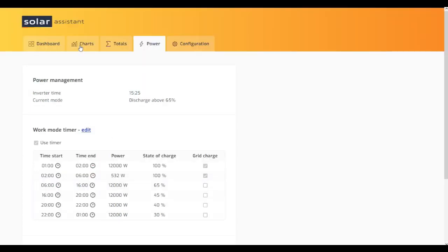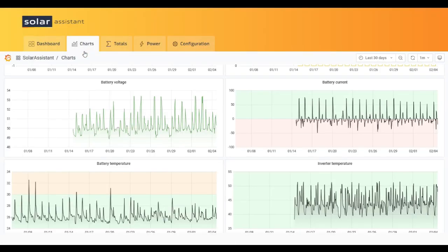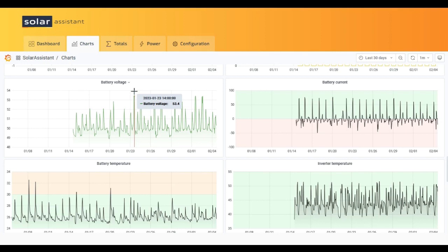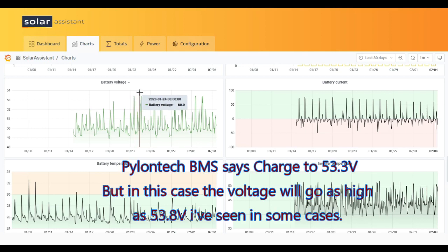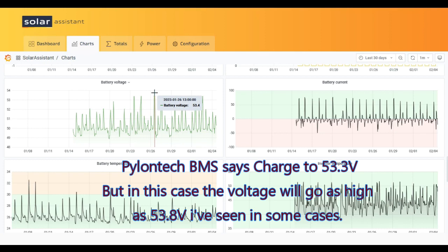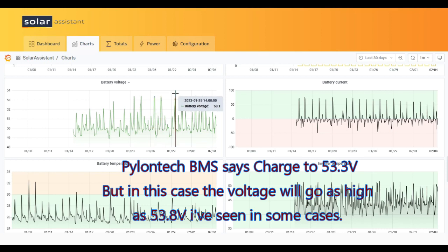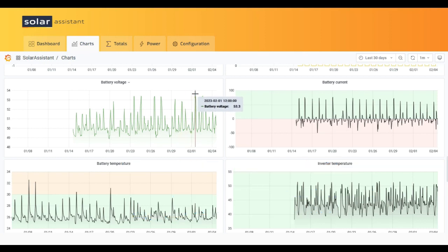What I could see is that I have overvoltage on the Pylontech. You can see 53.4V, 53.4V, 53.4V. Here I have rebooted the inverter and everything was okay.